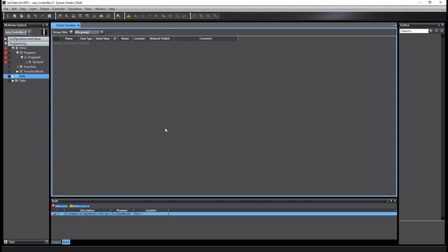Just like I mentioned, you're going to have common signals coming back for a component, whether it's a VFD, a conveyor, or even a pump or a valve, right? But let's say you had 9 attributes for each VFD, and say you had 3 VFDs. Well, there you go, right off the bat. You're going to have to create 27 global variables to cover all those attributes related to the VFD you're using. We can take those 9 variables for each VFD and access all 9 under one global variable. So how do we do that?